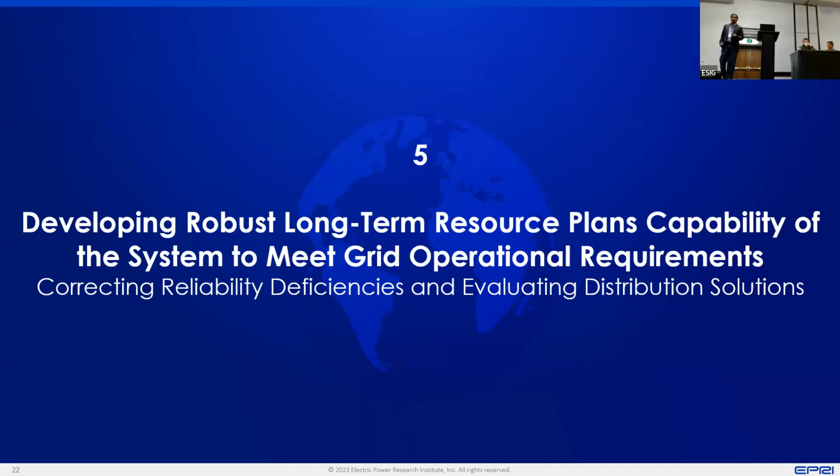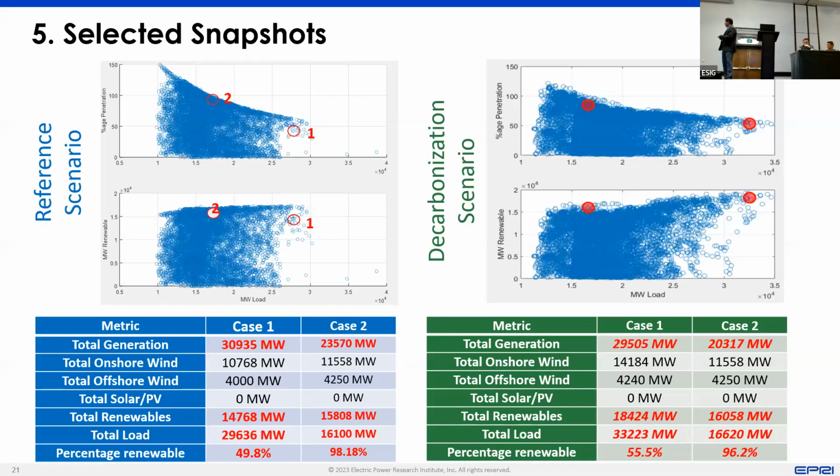We didn't get into stability, but obviously, once you have the scenarios picked, you can also run the stability analysis as well. And one point to make here is this analysis just tells you which generation dispatch and load level to pick. There is the manual step of actually building the PSS/E case. And for those of you who have actually done that, either for PSS/E or PSLF, you know the manual process or the pains that you have to go through to get the solved power flow. So that is a lot of manual work and that requires time.